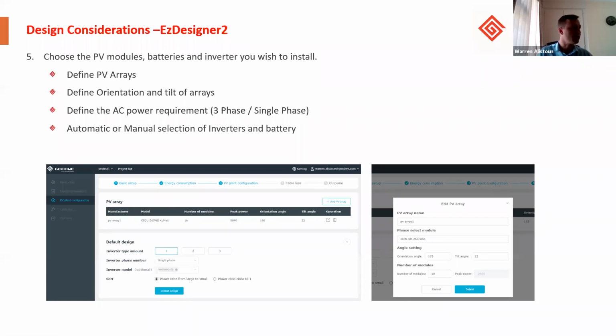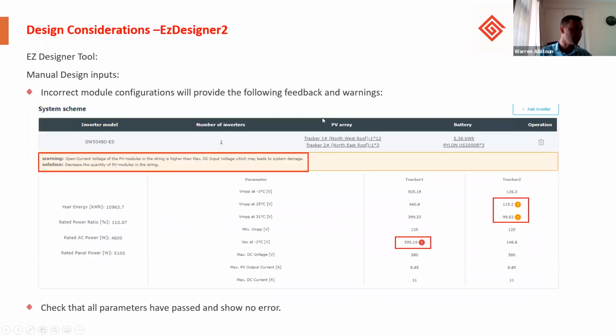So once you've selected which inverter, which batteries, we will get to this tab over here, which will give you warnings and tell you a little bit about the system design. I created this simulation to highlight a faulty design where I've put 12 modules in series on MPPT1, and we can see we exceed the input voltage, and it gives us a nice warning in red. I also undersized the number of panels on tracker 2 with only 3. And as we can see here, it's giving us warnings telling us we're under the MPPT range.